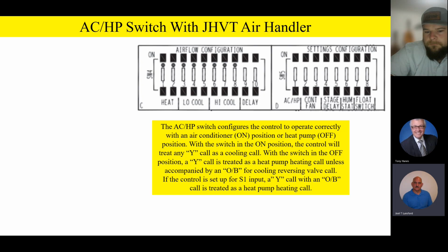So in summary, one more time, if that switch is in the on position and you get a Y call, it says, oh, I'm in the cooling mode. If that switch is in the HP or off heat pump position on a regular heat pump with this air handler and I get a Y call, it's a heating call, unless I have an O/B input, then it becomes a cooling call on a regular heat pump. But now hang on a second. With the HMH7, we energize the reversing valve in the heating mode, so we're able to deal with that as well. So now with the switch in the HP position and on the HMH7 outside, when we have a Y call, it's a heating call, just like any other heat pump.